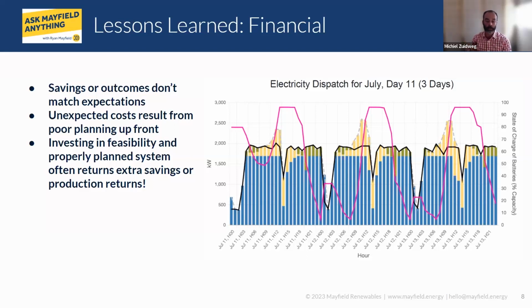They're charging the batteries up with the solar, so you can see in the middle of the day it goes up where the yellow is high. The gray dotted line means charging the batteries, and then the pink line drops in the afternoon to discharge the batteries when they're paying the high rates. In this utility, it's 28 cents a kilowatt hour from 4pm to 8pm roughly, and they're discharging the batteries to get a lot of that financial gain.